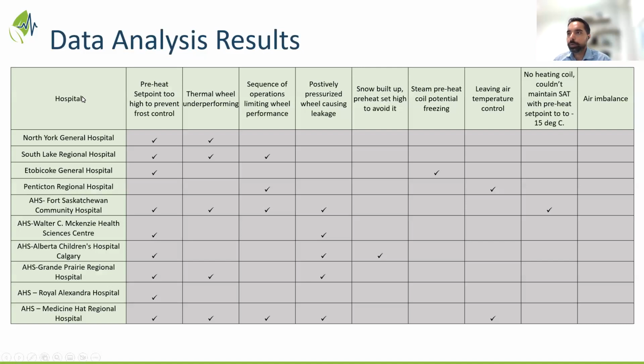Okay, here's the summary of the key findings in the majority of the hospitals. I'll go into each of them in more detail, just summarizing what those items are and where they've been found. When you look at the list of the hospitals, the single most predominant factor in a majority of them is that the preheat set point is too high. That's the single factor contributing most to inefficiencies or underperformance of the thermal wheels. Other factors are also important, but this is the most important and the simplest factor contributing to underutilization of the thermal wheels in facilities across Ontario, BC, and Alberta, and it's a consistent theme across most of the facilities.